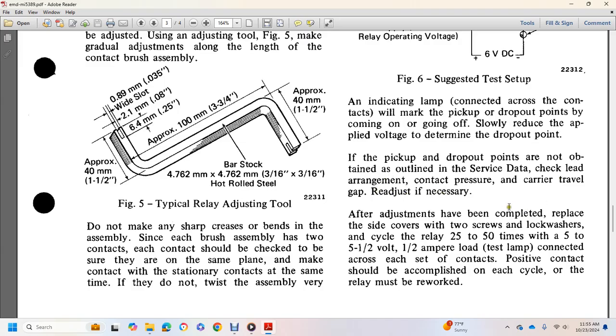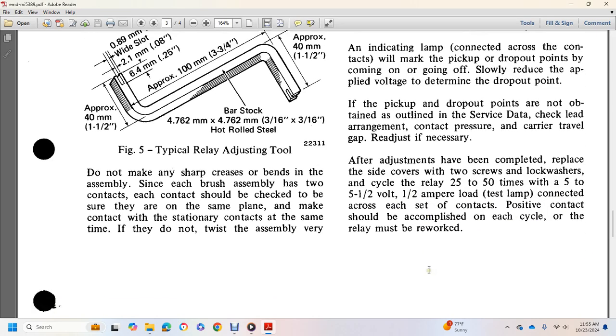After adjustment, replace the cover with the two screws and lock washers. Cycle the relay 25 to 50 times using 5 to 5-1/2 volts, 1/2 ampere load with a test lamp connected. Positive contact should be accomplished on each cycle; otherwise the relay must be reworked.